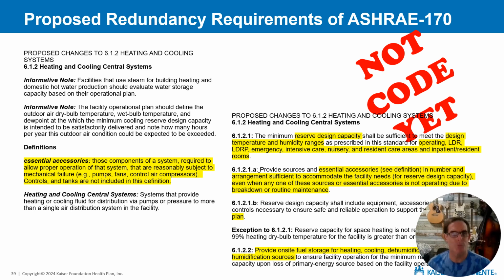One final example that's in the making here to potentially make matters a whole lot worse. The National Standard ASHRAE 170 currently has a proposal in public review right now to significantly increase HVAC redundancy. They're calling this reserve capacity. Among other things, this would require on-site fuel for heating and cooling and humidification. So right now we're only oversizing those fuel tanks for electrical. ASHRAE would like us to start sizing those fuel tanks also for heating. And for anyone who doesn't know that fun fact, natural gas usage at hospitals is usually more than the electrical. So this could double our fuel size requirement almost outright.